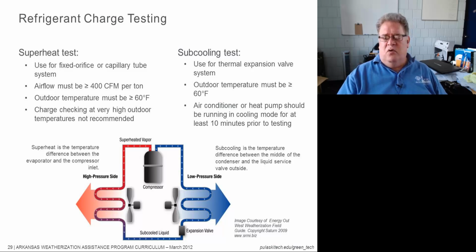And the air conditioner or heat pump should be running in cooling mode for at least 10 minutes prior to the test. We want that refrigerant to stabilize, those temperatures to stabilize. And subcooling is the temperature difference between the middle of the condenser and the liquid service valve outside. Your superheat is the temperature difference between the evaporator and the compressor inlet. Sometimes people get very mistaken on where to take these temperatures.